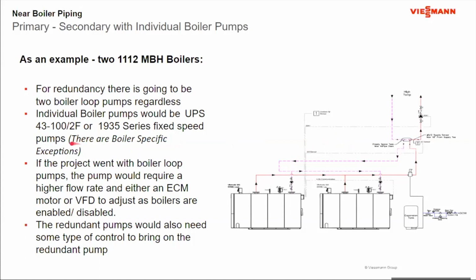Now, I also want to point out here, and this actually came out of a discussion from the previous class, there are boilers out in the market. We provide one of them that internally there are mechanisms to divide up internally to the boiler through isolation valves. So there are boilers on the market that are best served if I'm doing a boiler pump with a pump that has an ECM motor on it or a VFD. But that's something that's very specific. It's not the generic case. And most times the generic case is a fixed speed pump with something like this. Okay, so this becomes the other option.